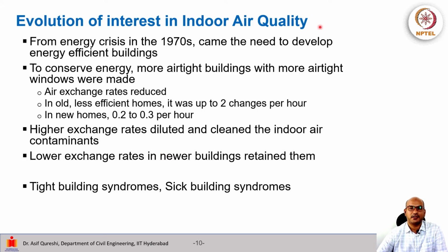So how did the interest in indoor air quality evolve? When there was an energy crisis in the 1970s, there became a need to develop more energy efficient buildings. That means if you are heating or cooling a building, there are fewer losses. So in that sense, people started to make more airtight buildings with more airtight windows and doors and the whole setting, so that the energy is conserved. As a result, the air exchange rates with the outdoor fresh air were reduced.